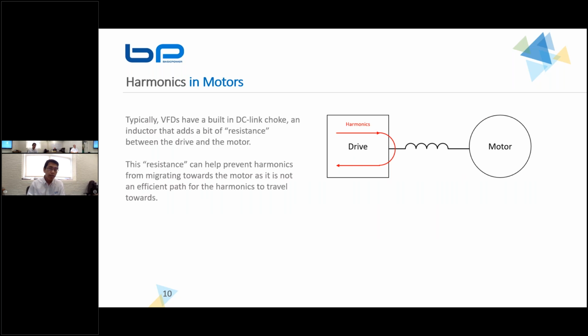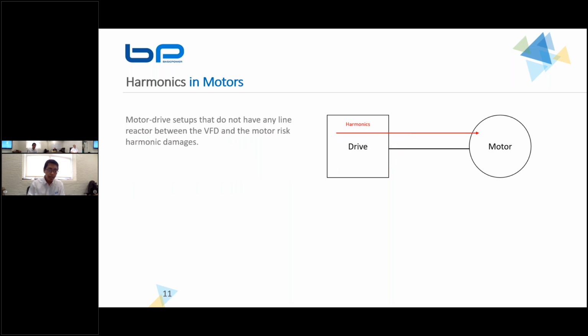Now, typically, if you have a drive and a motor setup, you can install something in the middle. It can be a DC link choke or just an inductor to add some impedance, right? It's just to prevent the harmonics from reaching that motor specifically. It's like a shield that tells the harmonic currents to migrate somewhere else, where it's not as easily maneuverable through that inductor. However, if you don't have any setup like this, the harmonics can just go straight through your drive and into your motor, and that's when you'll see the deterioration we mentioned before.